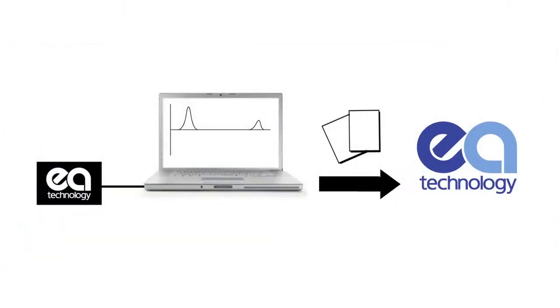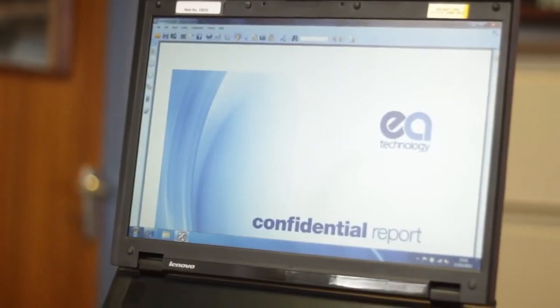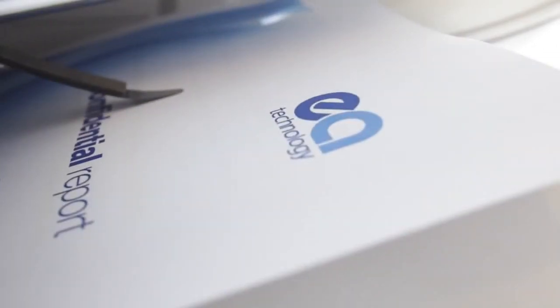Now, simply send the file to EA Technology. Our experts will carry out a detailed analysis of the data captured by the Cable Data Collector and provide you with a confidential report containing valuable management information on the severity of any partial discharge problems and assessment of the risks of the cables under test failing in future, and recommendations for any remedial or replacement actions that may be needed.